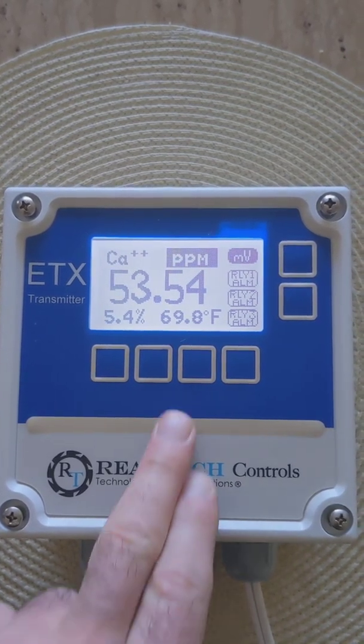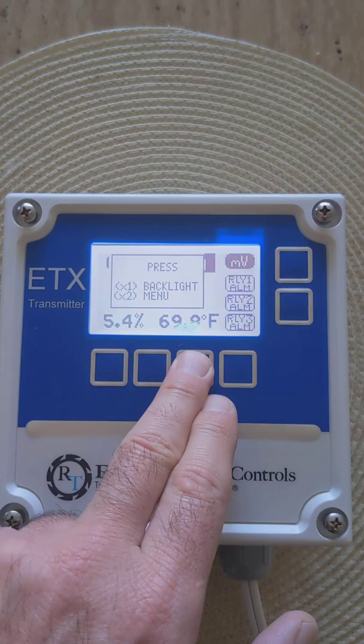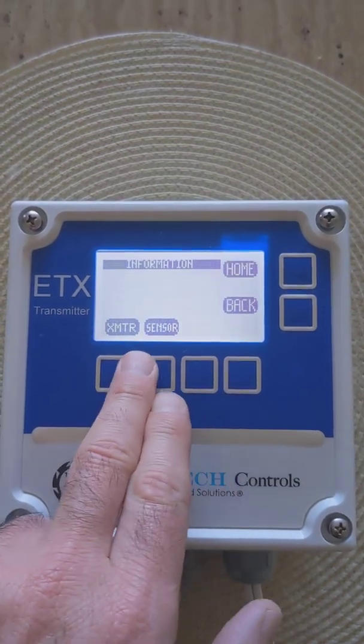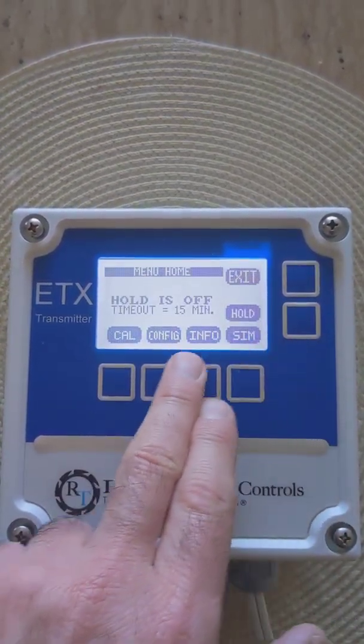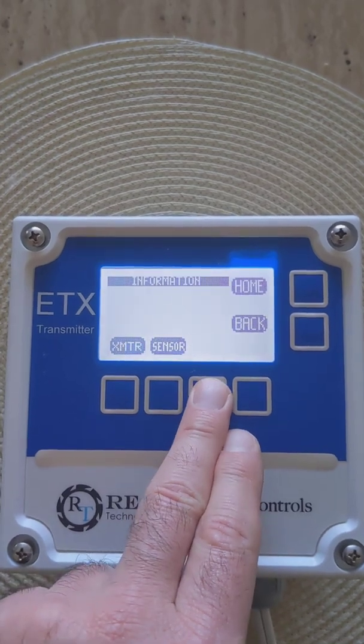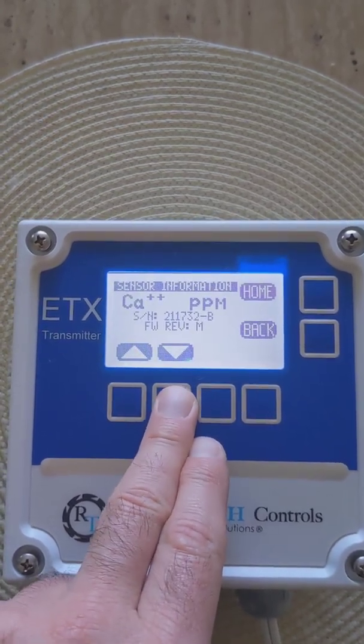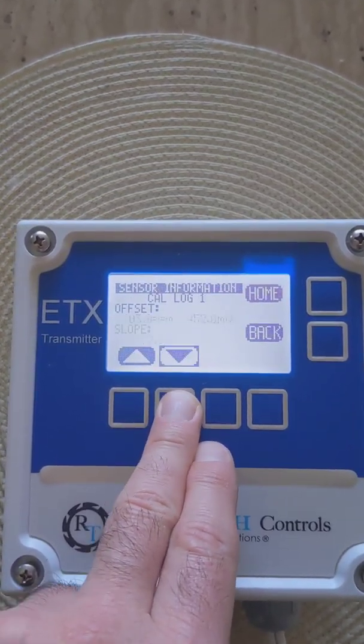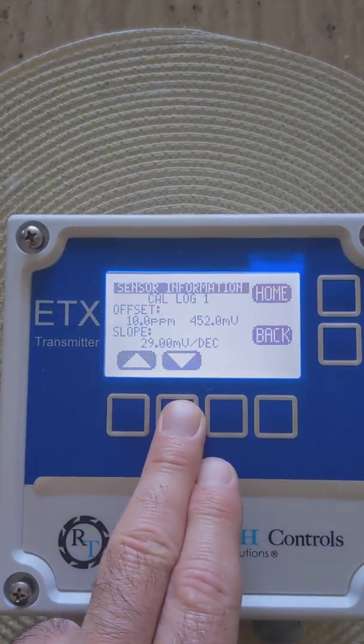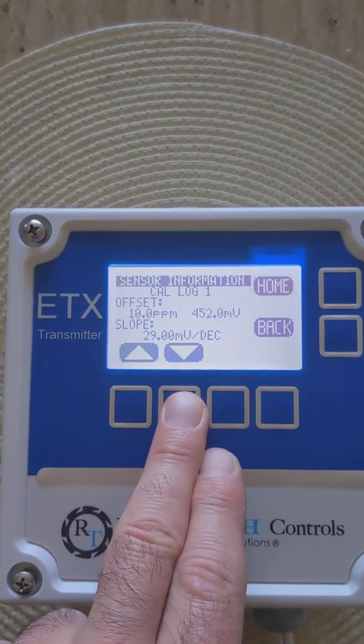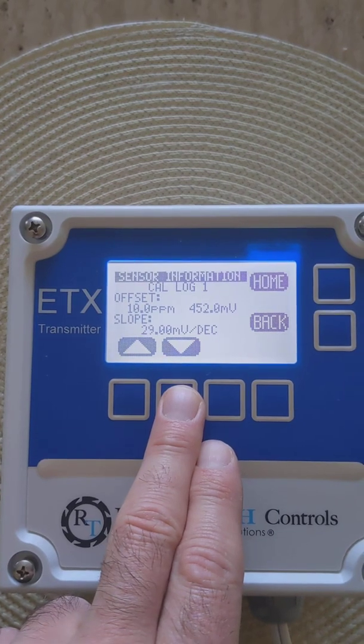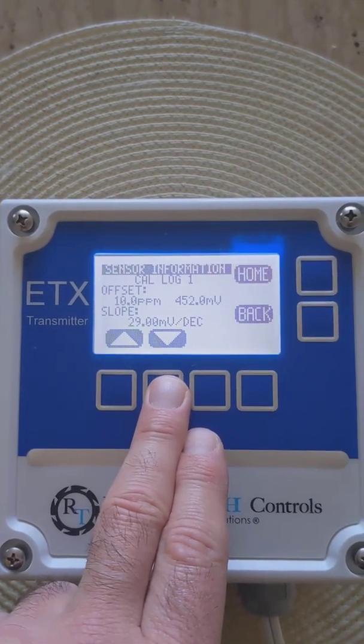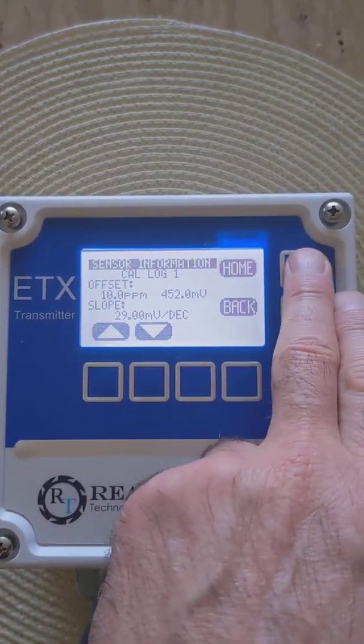And if I want to see that value again in the system, you go to, sorry, I went too quick, you go to Information, Sensor, and you scroll down to your log 1, and there is the information that you just entered for the factory calibration. And that is how you reset the factory default of the water hardness sensor.